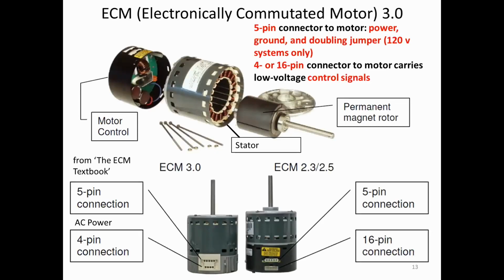This is a diagram actually from the ECM textbook, which is freely available online if you want to know a lot more about ECMs than you need to know, but I want to point out a couple of things. There is a control unit, which in this case is part of the ECM. There is the stator, which does not rotate and has a large group of coils around the circumference. And there's a permanent magnet rotor. If you're familiar with induction motors, you'll notice there are no coils on the rotor because it's not an induction motor. It's a permanent magnet motor. There are permanent magnets laid out, and they alternate in orientation, north-south, south-north, north-south. And as the magnetic field rotates around this circle of coils, the permanent magnet rotor tracks that rotation and remains synchronous with it.